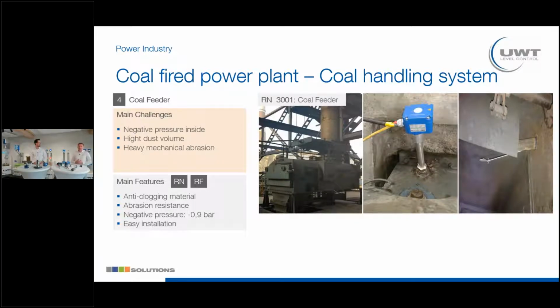We had to mount the sensor sidewards, so we could not use a rope version - we had to use almost a standard shaft version. And what you can see on the right picture, we installed a little bit of protection for the shaft here, again to avoid any influences or mechanical damages.